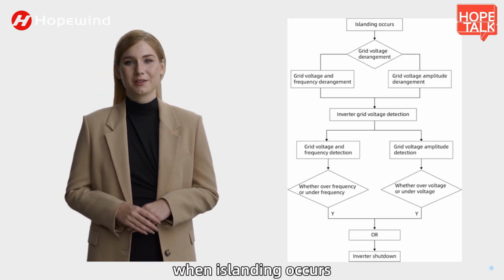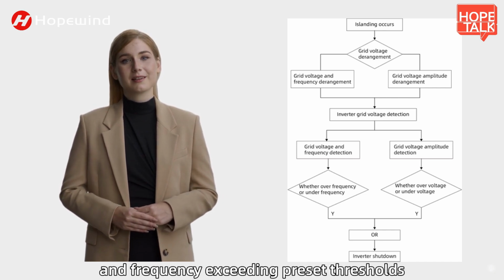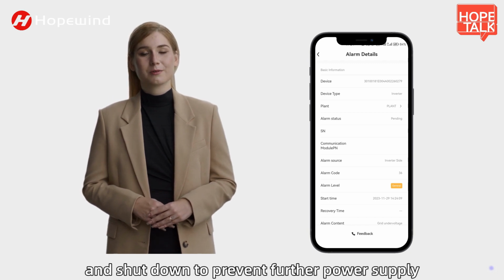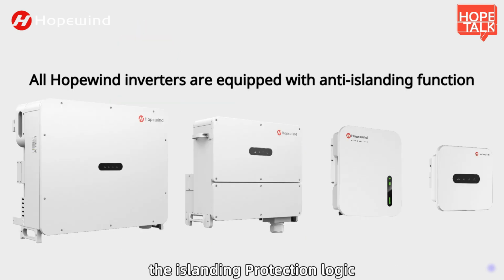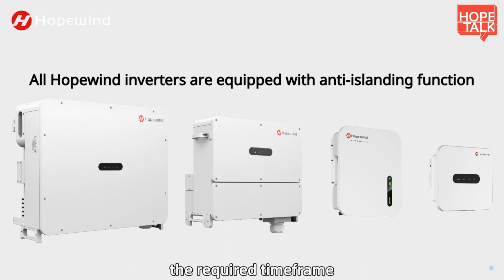When islanding occurs, the Hopewind inverters detect grid voltage and frequency exceeding preset thresholds. Then the inverters disconnect from the grid and shut down to prevent further power supply. Simultaneously, they trigger alarms through our HopeCloud app. The islanding protection logic of Hopewind inverters is designed to swiftly respond to grid disturbances and ensure a safe disconnection from the grid within the required timeframe.